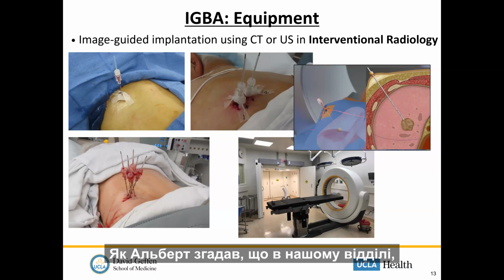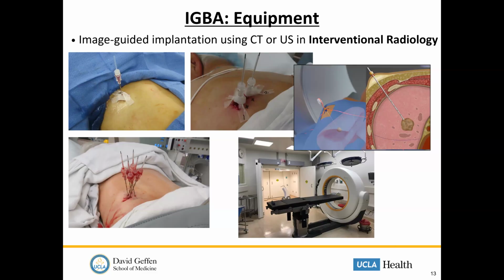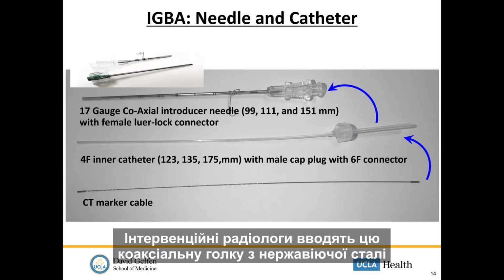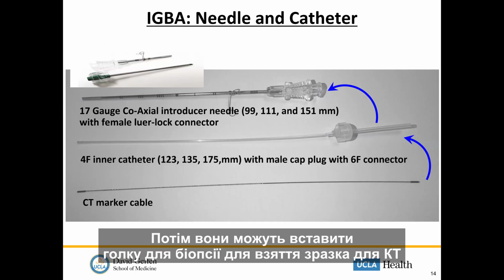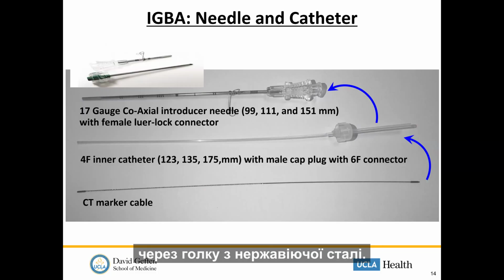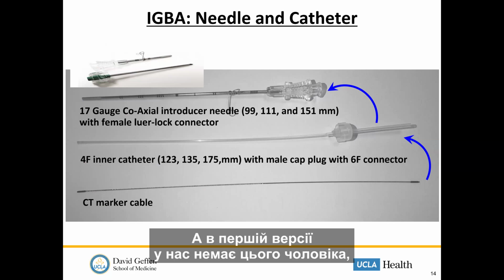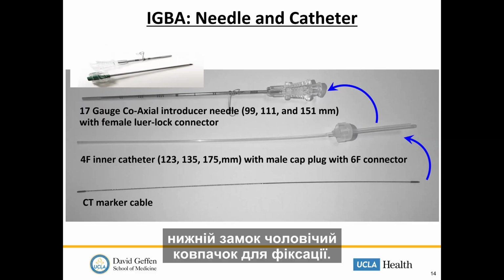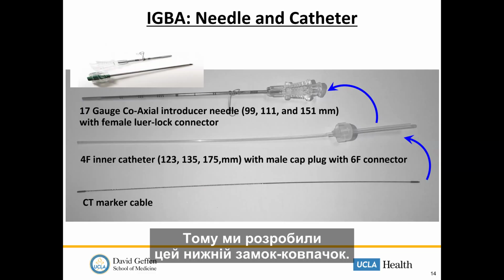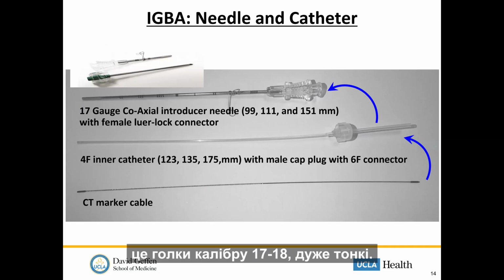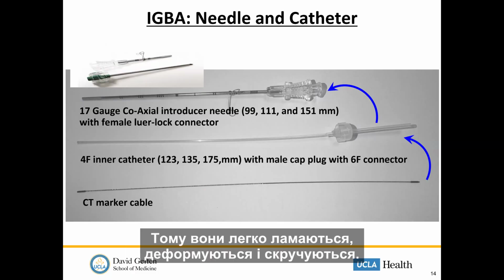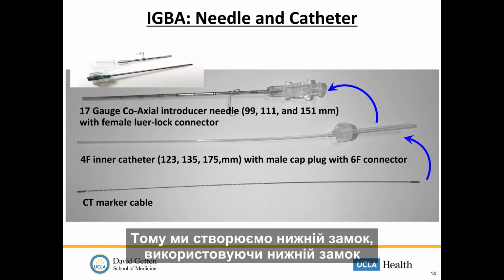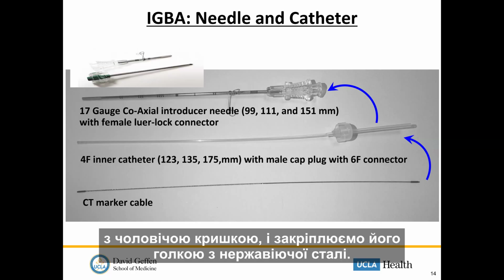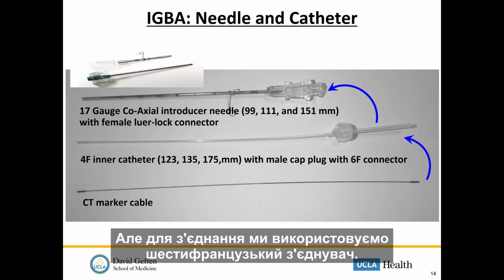As Albert mentioned, in our department we developed these brachytherapy catheters. The interventional radiologist places this 17-gauge coaxial stainless steel needle under CT guidance, and they remove the stylet. Then they can put in the biopsy needle for the tissue sample through this stainless steel needle. But we place the brachytherapy catheter. We designed the 4 French inner catheter, and then place it into the stainless steel introducing needle. In the first version, we didn't have this male Luer lock cap to secure it, so we developed this Luer lock cap. The problem is the 4 French catheter, which fits the 17-gauge needle, is very thin, so it's easy to break, bend and kink. So we created a Luer lock secured using the male cap plug Luer lock and secured with the stainless steel needle. For the connection part, we use a 6 French connector.